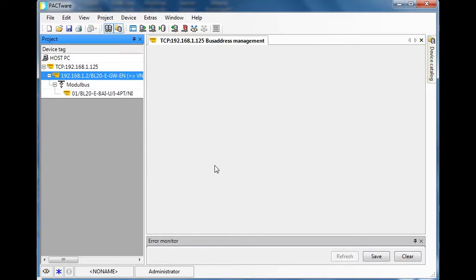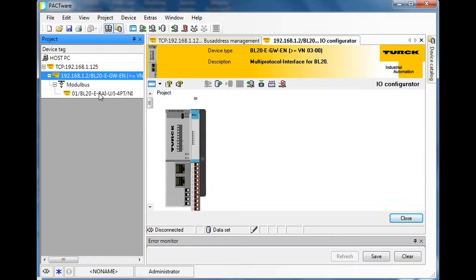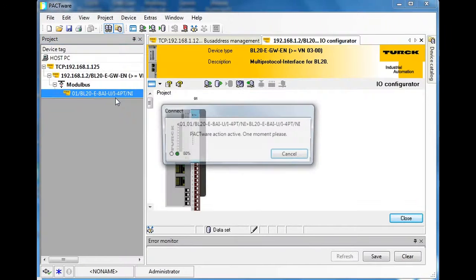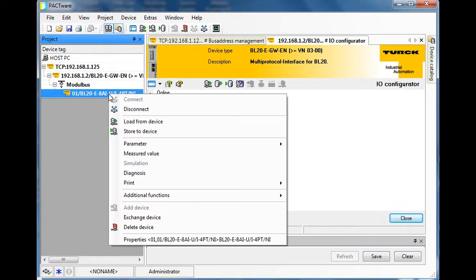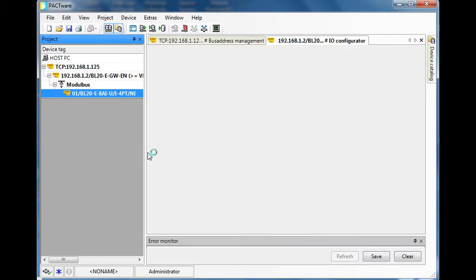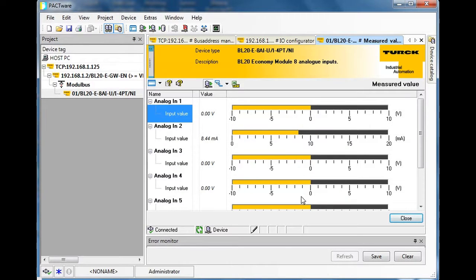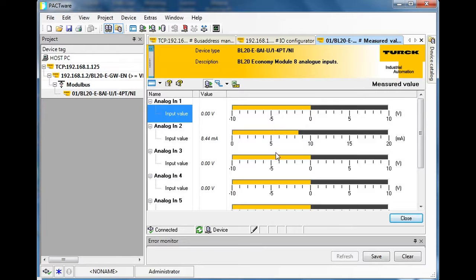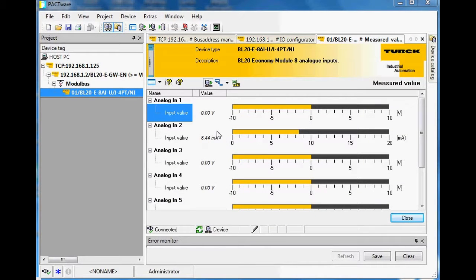Let me double-click on this to show you a picture of what my node looks like. If I want to go online, I right-click on the IO slice and go to Connect. Then I can right-click and go to Measured Value. You can see this has an eight-channel analog input card — inputs one through eight — and on channel number two I've got an analog value coming in.